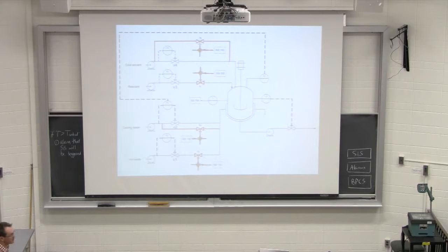Our cooling water we want to fully open. Now there's a control valve in the line from the cooling water pump into the jacket, and we cannot rely on the position of that valve.